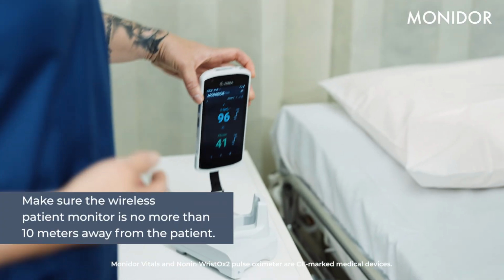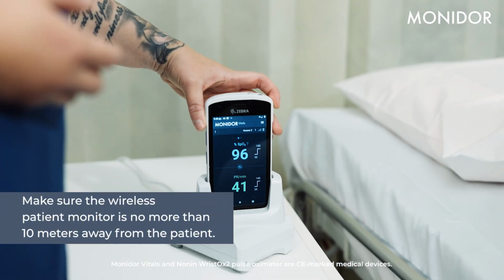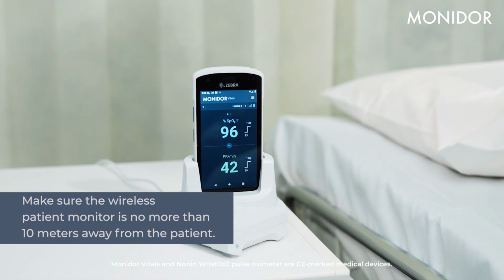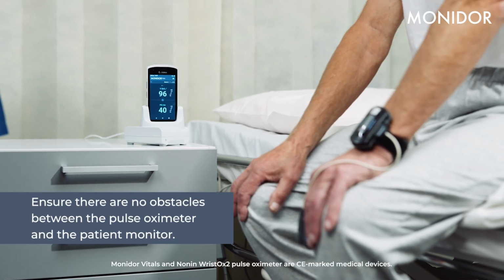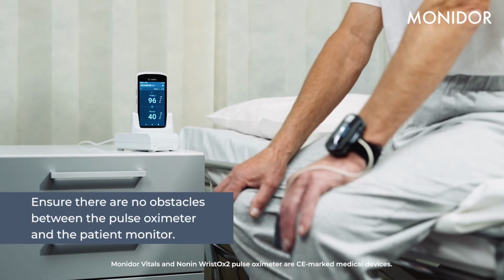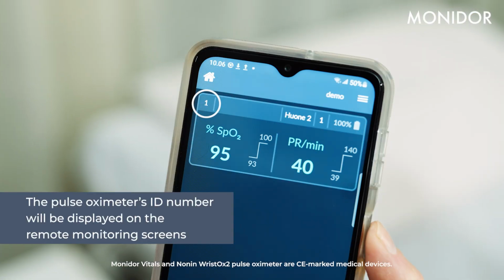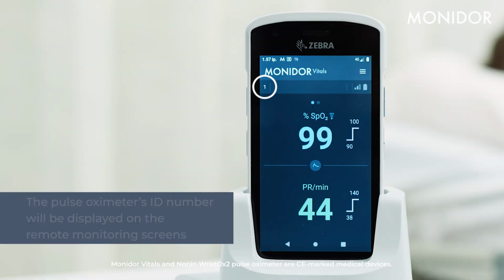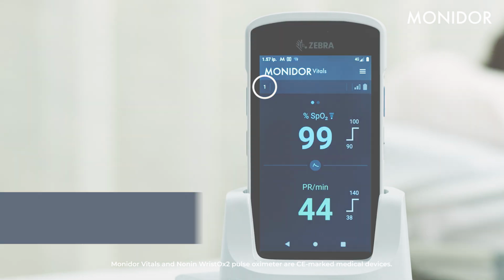Make sure the wireless patient monitor is no more than 10 meters away from the patient. Ensure there are no obstacles between the pulse oximeter and the patient monitor. The pulse oximeter's ID number will be displayed on the remote monitoring screens and on the patient monitor.